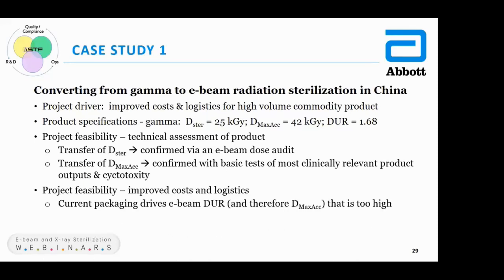Then we looked, from the feasibility stage, at how to improve cost and logistics. The way the product was packaged - the primary package and the corrugate shipping materials that went to the gamma facility - the current packaging derived an e-beam dose uniformity ratio, and therefore the maximum dose the product would see was higher than 42 kilogray for a sterilization dose of 25.